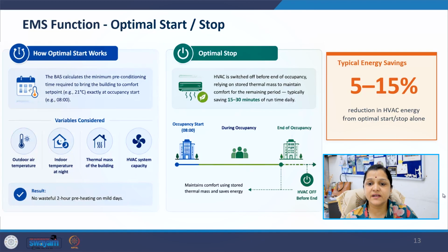The optimal start and stop of the energy management system calculates the minimum preconditioning time required to achieve indoor comfort conditions exactly when occupancy begins. The building automation system considers outdoor temperature, indoor temperature, building thermal mass, and HVAC capacity before determining startup time. This prevents unnecessarily early operation during mild weather conditions. Optimal stop works in the opposite manner. HVAC systems shut down before occupancy ends while relying on stored thermal energy to maintain comfort temporarily. The slide indicates that optimal start and stop strategies can reduce HVAC energy consumption by approximately 5 to 15%. This function demonstrates how the building automation system uses predictive logic rather than fixed schedules alone.